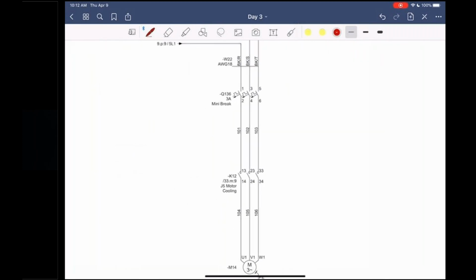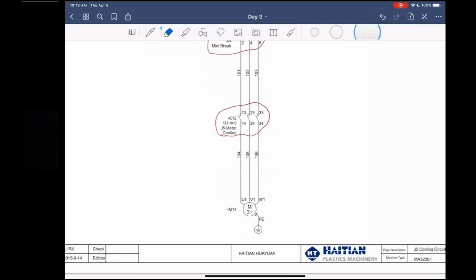The J5 cooling motor is the only induction motor in this machine. And when you energize the drive by turning that little pump motor symbol on, it actually energizes this motor and it runs constantly. It has a breaker here. It's Q136, which is a 3 amp breaker. And K12 is actually the circuit that when you hit the drive closes the contacts, so this motor will start running.